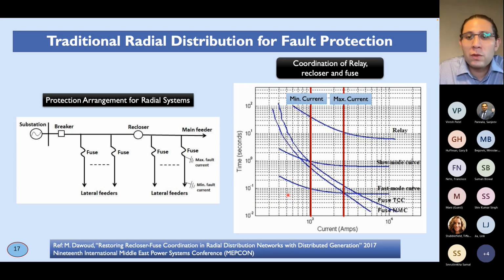Then we have the fuse operation, which operates to clear the fault. If the fault is not self-cleared, this is when the fuse acts. After the fuse acts, if the fault is not cleared, the recloser has a slow mode operation, which acts as a backup of the fuse. As we can see in the figure, here is the slow curve. We have the fuse curves that come here, and then we have the slow mode curve. The latest one is the relay. The relay is the last one to operate, as a double backup, in case the slow mode recloser does not operate, or it disconnects or connects and keeps identifying the fault in the grid. Basically, if the recloser in slow mode fails to operate, then the circuit breaker upstream should operate immediately as a backup of the recloser, as we can see in the figure.